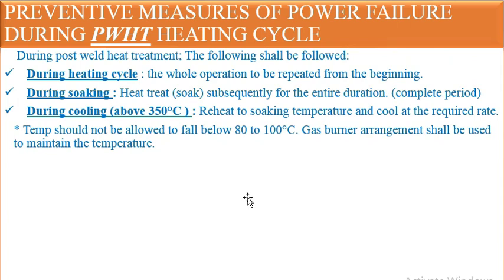Preventive measures during PWHT power failure: if the power fails during the heating cycle, the whole operation must be repeated from the beginning. If the failure occurs during soaking, the treatment must be repeated for the entire duration. If the failure occurs during cooling, reheat to the soaking temperature and cool again at the required rate.